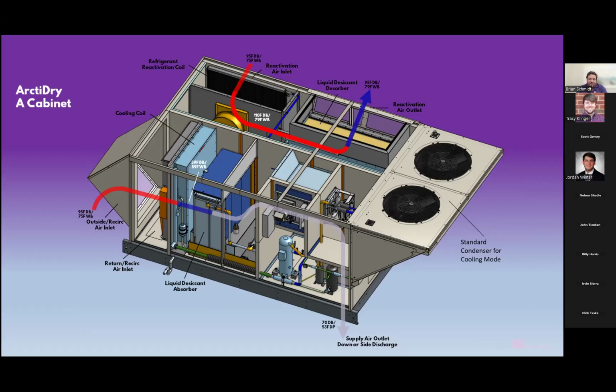So the air passes through the filter bank, passes through the coil. Next, it's going to see the absorbing pad. Again, concentrated desiccant is flowing from the top of the pad down. It's picking up moisture and it's diluting that concentration as it goes down. The air is then going to pass through the winter heating module. So this is gas, electric, hydronic, or heat pump. So if you do need to reheat more than the pad can provide, we can utilize that winter heating module to reheat to whatever space condition you're looking for. But that is primarily a winter heating module. And then you're going to pass through the ECM supply fan, 3 inches of static, and we have side and down discharge. On the other side of that wall is our regen side.